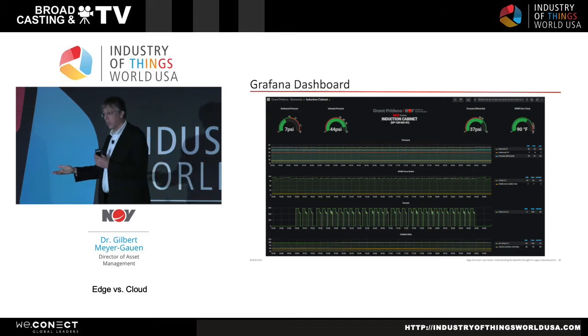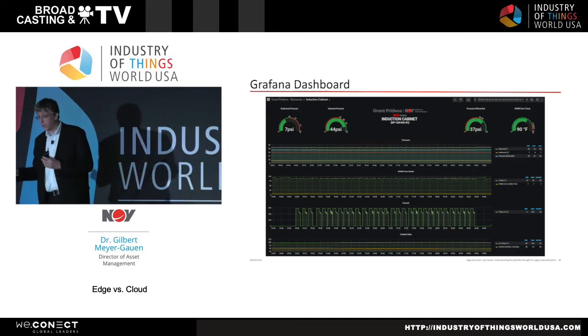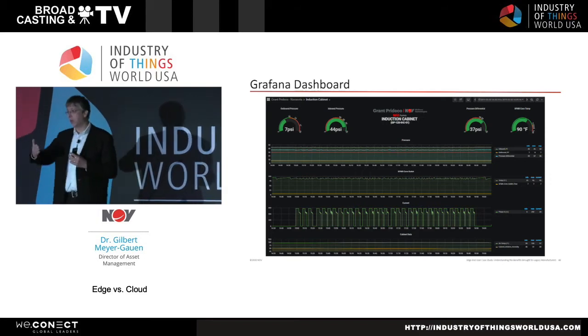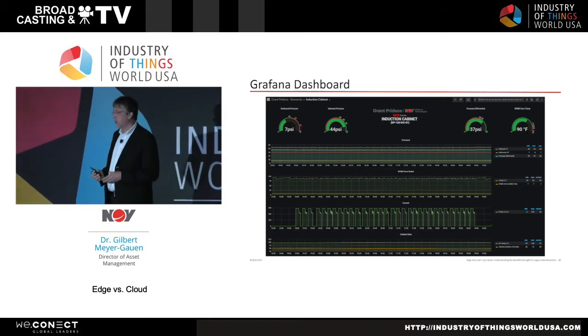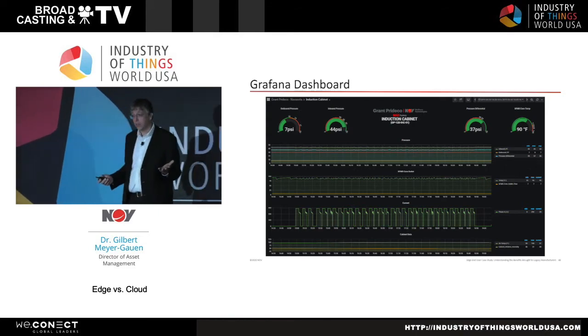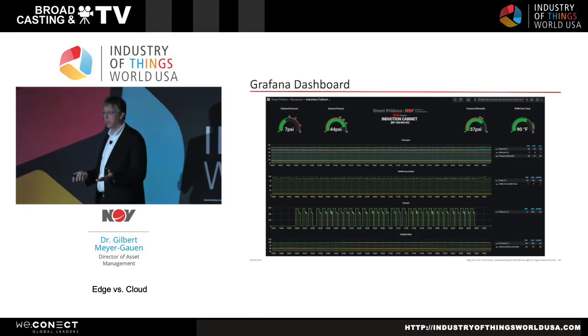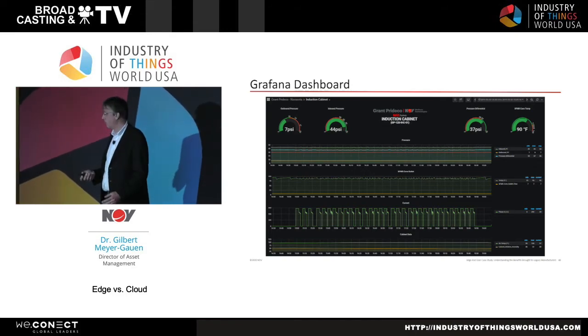And there are sensors that can do this. There are moisture sensors that are very, very sensitive. So we are working on a scenario where we can put moisture sensors at different areas and immediately at least raise an alarm for the operator when it detects moisture so that the operator can turn off the entire system and we no longer have this trickle effect. So speed can really matter in these cases. Not everything has to be in the cloud. Sometimes it makes more sense to move it closer to the machine, and this is one example here.